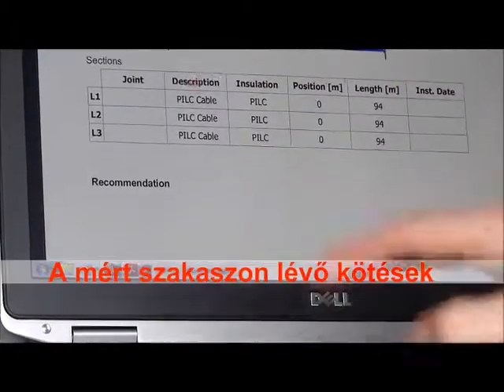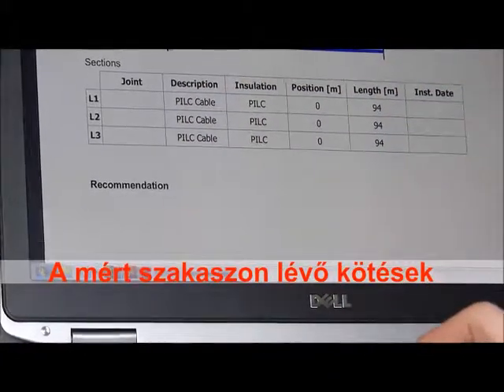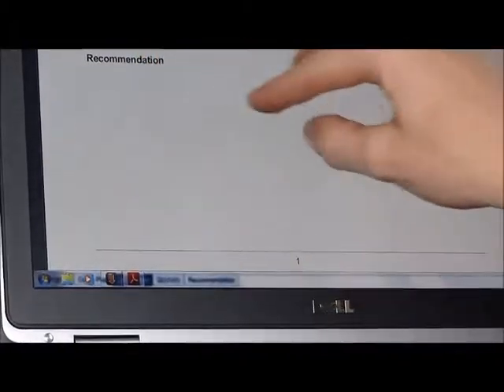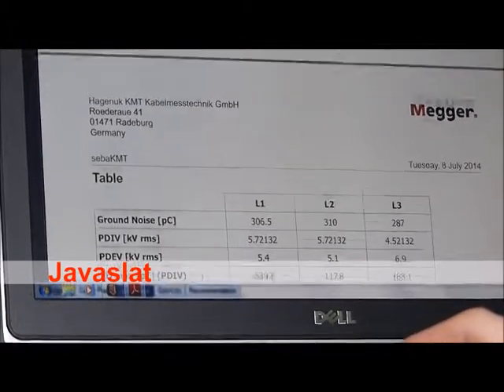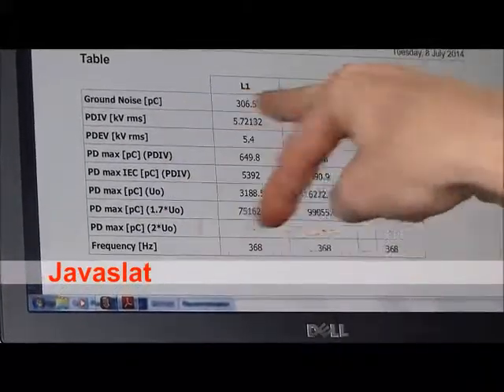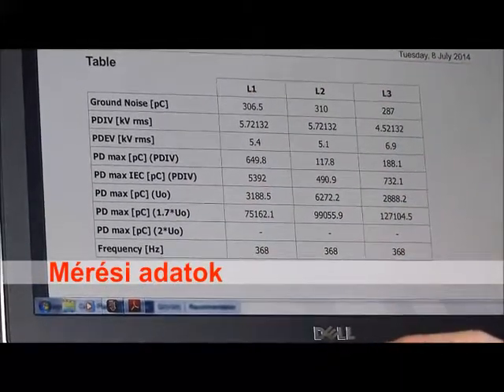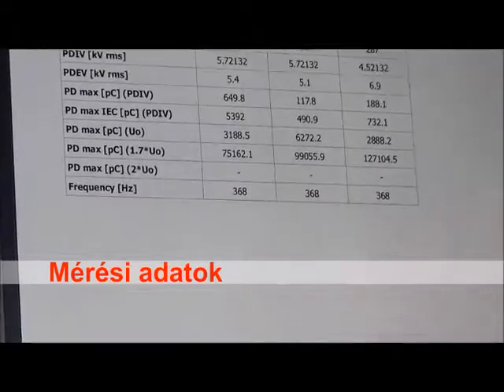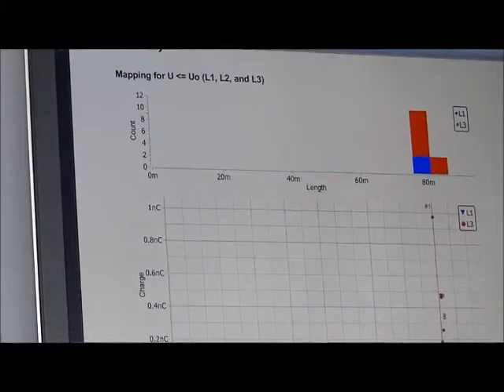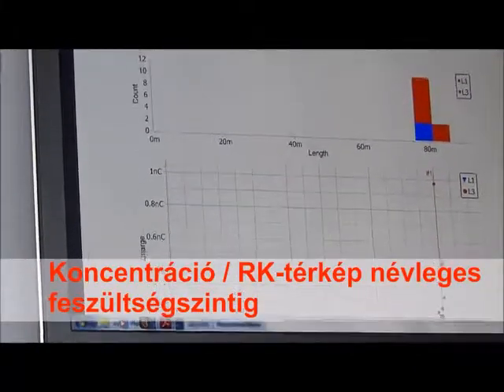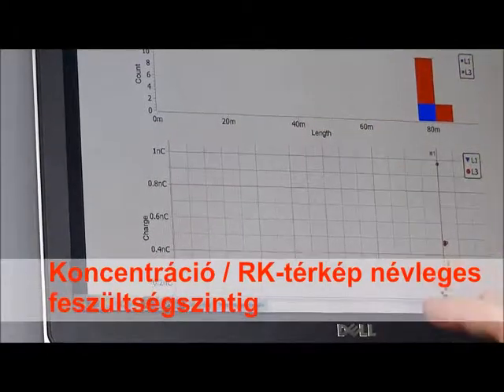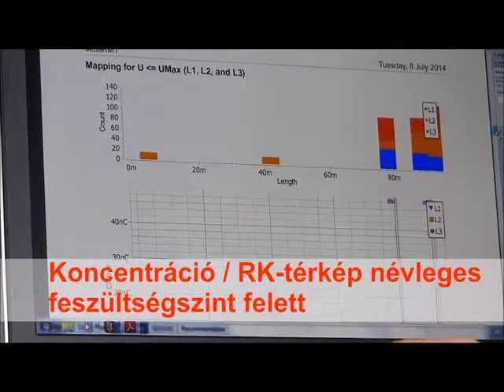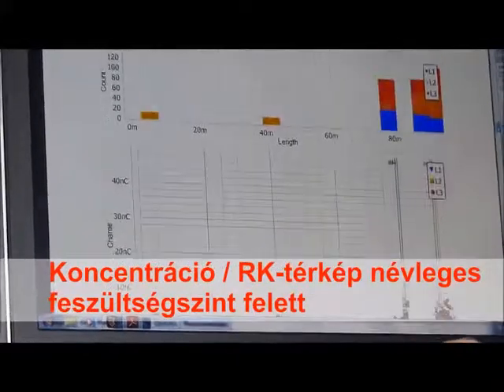It would be much longer if you have more joints in here. Then you could write down the recommendations already in here. You see the partial discharge inception and extinction voltage, PD max, similar compared to the OWTS. Then you have the concentrations here up to the nominal voltage, and then the concentrations for the higher test voltage.